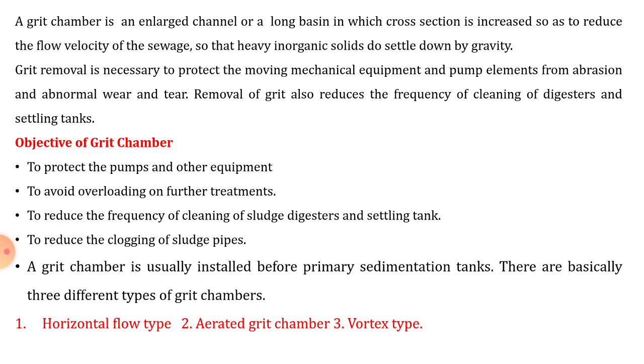The grit chamber is an enlarged channel or long basin in which the cross-section is increased so as to reduce the flow velocity of the sewage, so that heavy inorganic solids settle down by gravity. Due to the enlarged channel and long basin, velocity is reduced, and as velocity reduces, inorganic solids heavier than water start settling by the action of gravity.